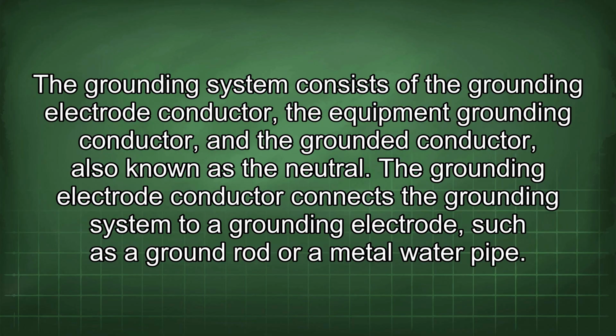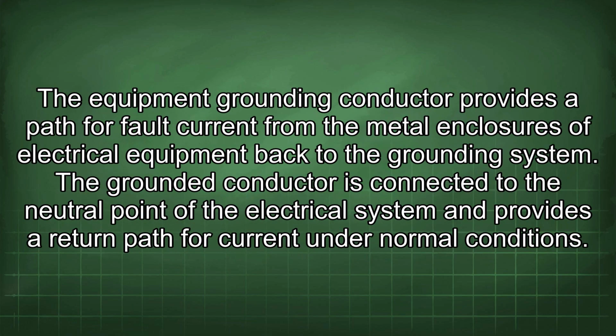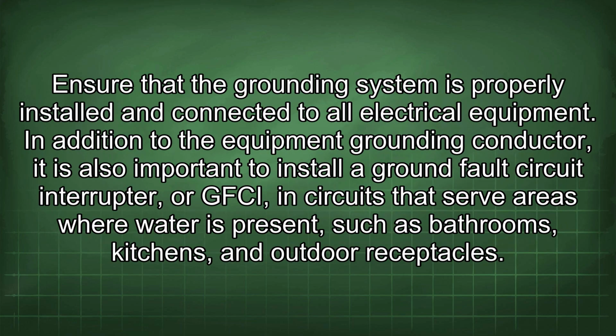The grounding system consists of the grounding electrode conductor, the equipment grounding conductor, and the grounded conductor, also known as the neutral. The grounding electrode conductor connects the grounding system to a grounding electrode, such as a ground rod or a metal water pipe. The equipment grounding conductor provides a path for fault current from the metal enclosures of the electrical equipment back to the grounding system. The grounded conductor is connected to the neutral point of the electrical system and provides a return path for current under normal conditions. Ensure that the grounding system is properly installed and connected to all electrical equipment.